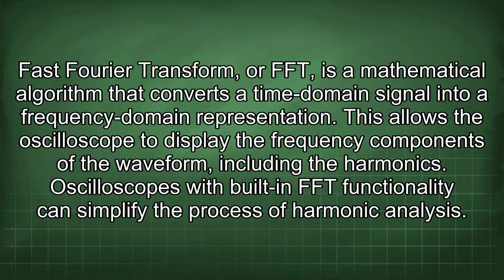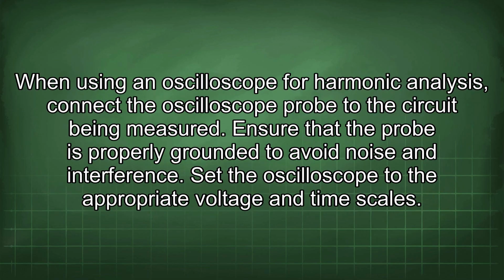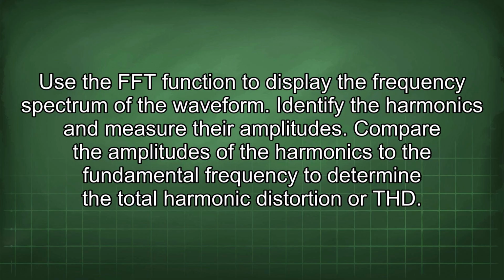Fast Fourier transform, or FFT, is a mathematical algorithm that converts a time domain signal into a frequency domain representation. This allows the oscilloscope to display the frequency components of the waveform, including the harmonics. Oscilloscopes with built-in FFT functionality can simplify the process of harmonic analysis. When using an oscilloscope for harmonic analysis, connect the oscilloscope probe to the circuit being measured. Ensure that the probe is properly grounded to avoid noise and interference. Set the oscilloscope to the appropriate voltage and timescales. Use the FFT function to display the frequency spectrum of the waveform. Identify the harmonics and measure their amplitudes.